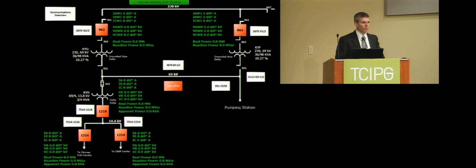If we wanted to do some data checking, on the bottom left-hand corner, coming out of the step-down transformer to the 14 kV system, we have current flowing out of it, well, it's breaker 1218, a relay measuring the current flowing out of it, and then to 2 feeders below it, and we can do some quick summations of those.